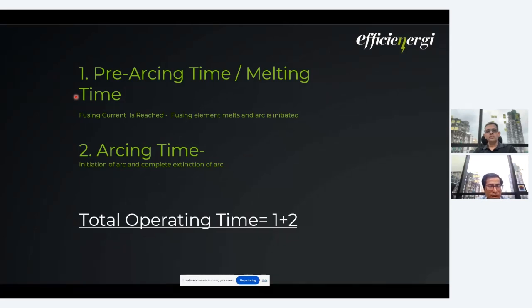So we know that there is a pre-arcing time, which is also called the melting time. What exactly does this mean? When a fault current goes beyond the fusing current, the fusing element will melt, and then there is an initiation of arc. So this time starts from the fault current and ends where the arc is initiated, that is, where the fusing element completely melts down. Then comes the arcing time. Arcing time is from the initiation of the arc to the complete extinction of the arc. So the time between these two is called the arcing time. These two added together give the total operating time, which is the complete fault clearing time of the fuse.